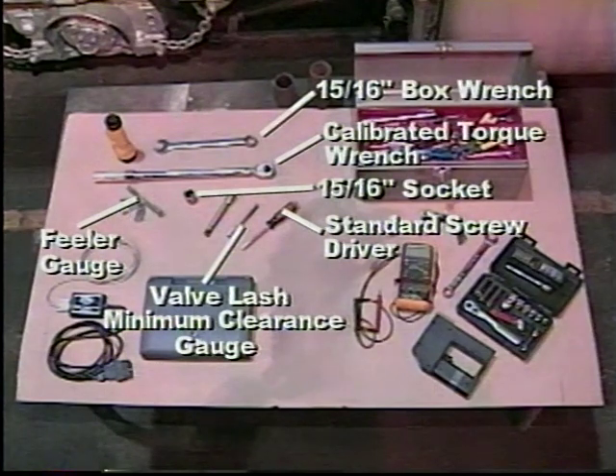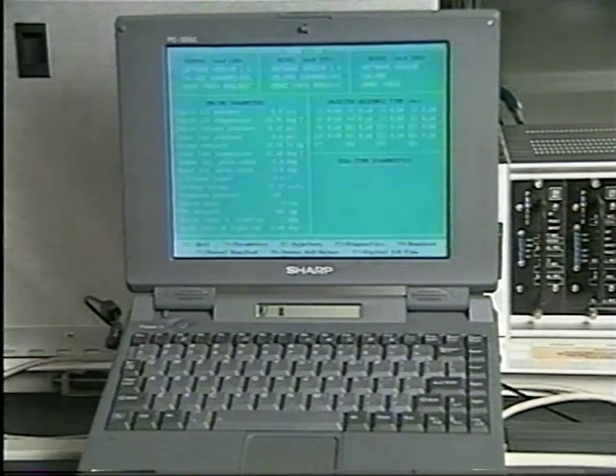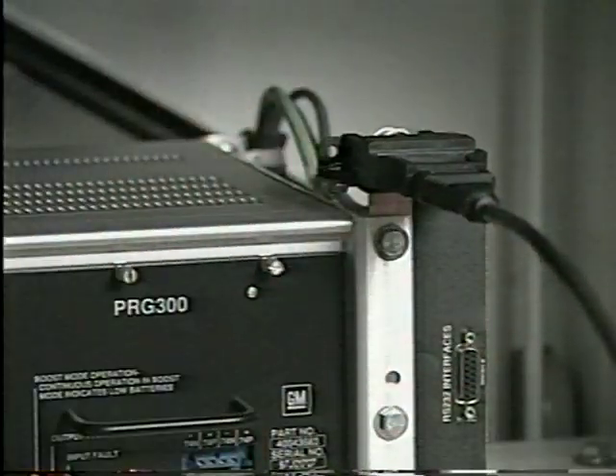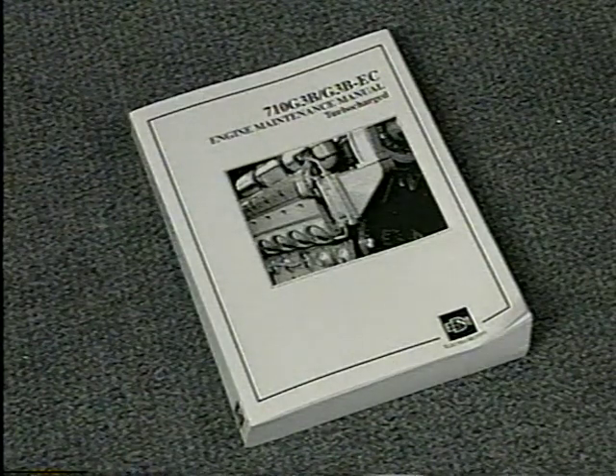The tools we will be using today to perform our engine adjustments include a 15/16 box end wrench, a 15/16 socket, preferably 1/2-inch drive, a calibrated torque wrench of at least 100 foot-pound capacity, a standard slot screwdriver, a 1 or 1.5 thousandths of an inch feeler gauge or piece of shim stock, a valve lash minimum clearance gauge, a laptop computer with the PC reader software and connector cables, and your engine maintenance manual.